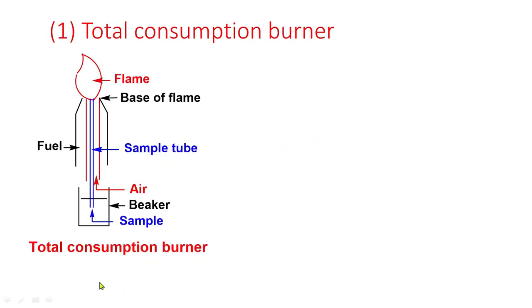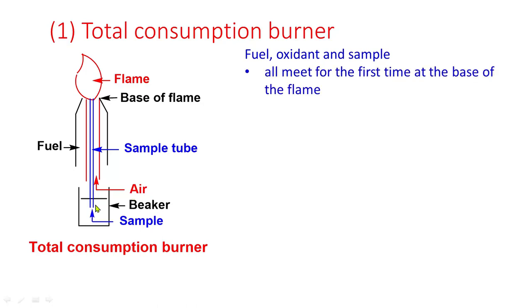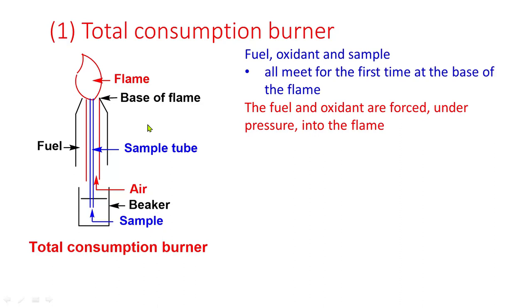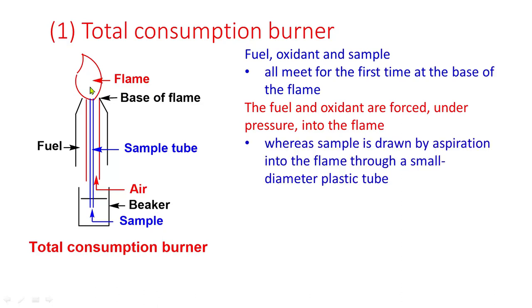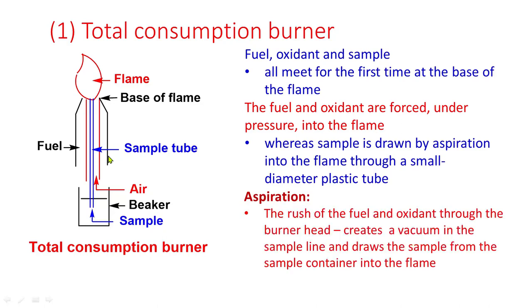In the total consumption burner, fuel, oxidant, and the sample all meet for the first time at the base of the flame. Fuel and oxidant are forced under pressure into the flame, where the sample is drawn by aspiration through a small diameter plastic tube. The rush of fuel and oxidant through the burner head creates a vacuum in the sample line and draws the sample from the sample container into the flame.